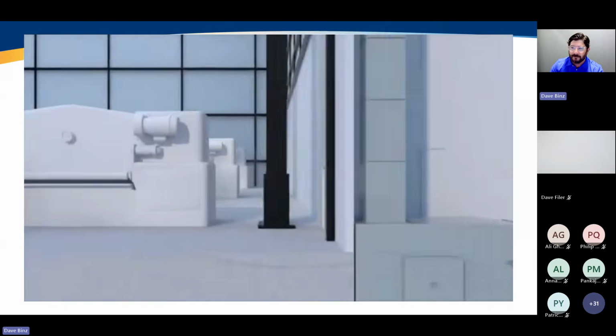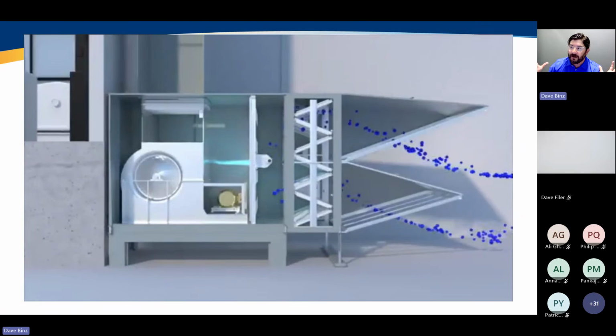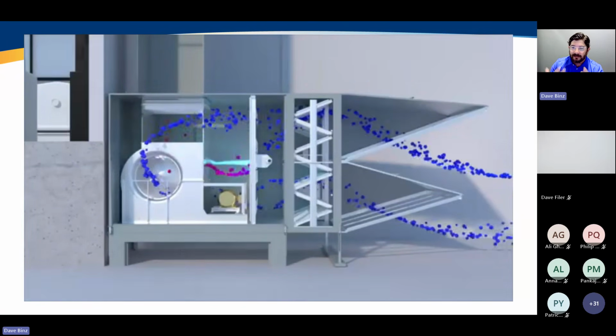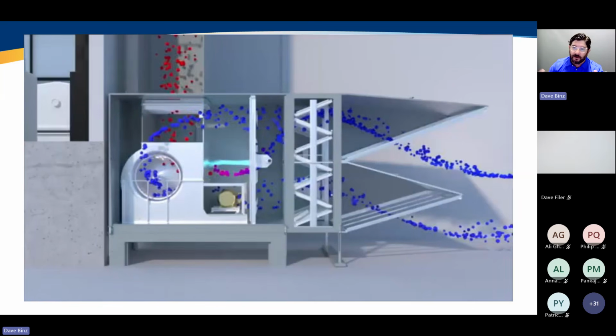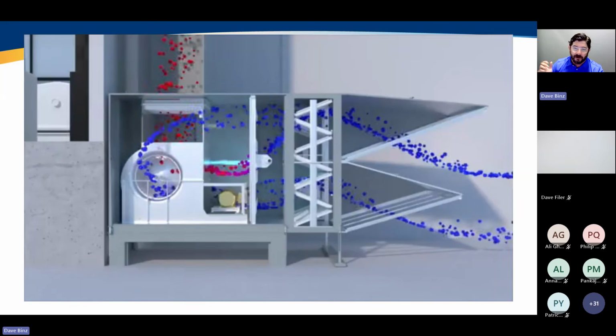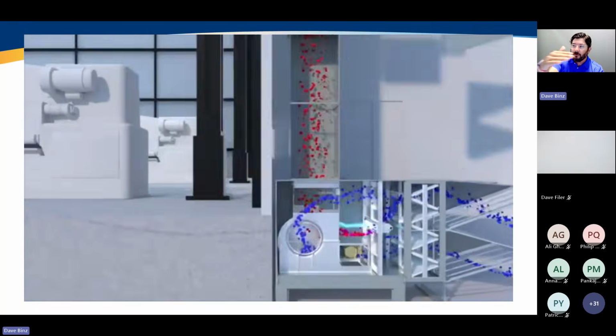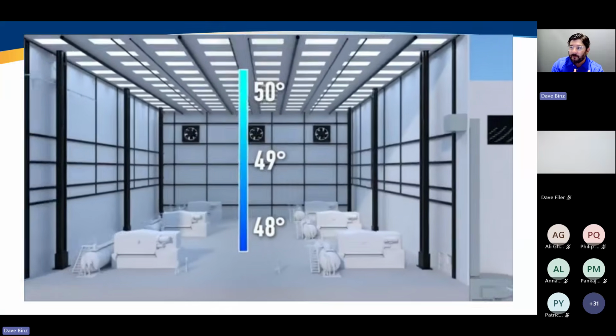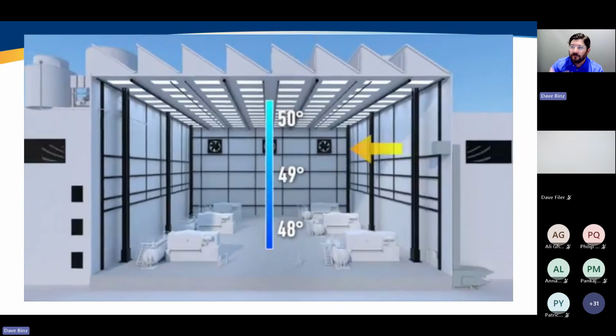And how do we solve those ventilation problems? With a makeup air solution, right? We want to make sure we're actually providing that ventilation through a tempered, filtered makeup air solution. So we're going to bring in that 100% outside air. We're going to filter it. We're going to temper it. We're going to heat it. We're going to deliver it to the space. So now we're going to be solving that negative pressure and what seems to be a heating problem with ventilation. So we're going to provide tempered ventilation. We're going to provide a more ambient level temperature into the space. And so I may not necessarily be heating the space, but I'm actually tempering the ventilation. And so now what seemed to be a heating problem was actually a ventilation problem. And so that's really where tempered makeup air comes into play.